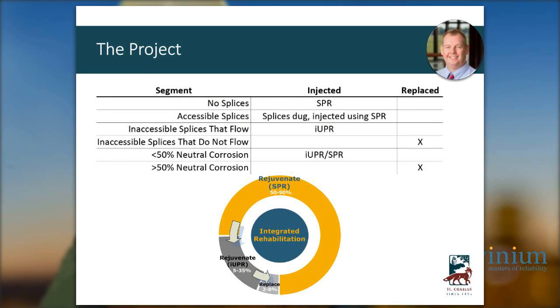I wanted to talk a little about the injection process. Novinium offers two different processes. One is called sustained, which we prefer and prioritize — you inject the fluid under higher pressure, and for most of our span lengths it takes an hour, hour and a half, to two hours, with the fluid going from one end of the cable to the other. You seal the ports, put the elbows back on, put the cable back in service, and move to the next one. Sometimes we get 3 or 4 spans done per day using the sustained method.